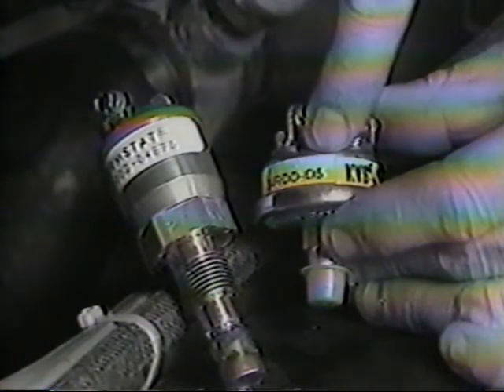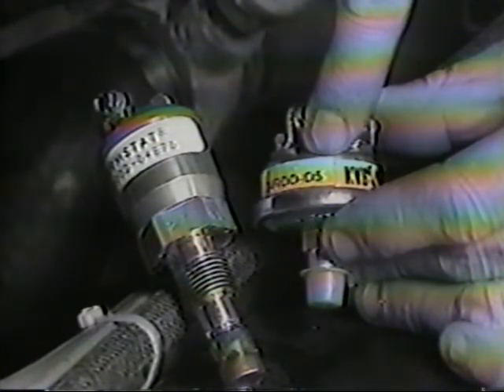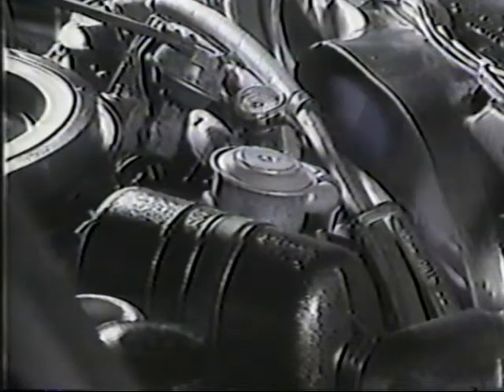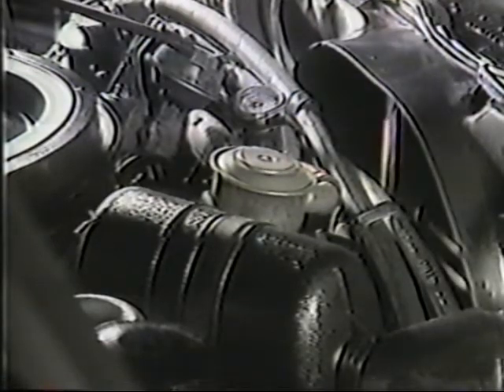The alarm temperatures and pressures, however, are shown in the various KYSOR publications. Compare the stats on your engine with the listings in the back of these KYSOR publications, EP7 or EP5 for 9033, 9032, and 9031. Use EP8 for the 9038, 9041, 9042 series of systems. The engine listings are according to module part number, since the pressure stat is inside the module. Remember, more false alarms and shutdowns are caused by incorrect alarm stat and pressure stat application than any other factor. You must have the correct item.